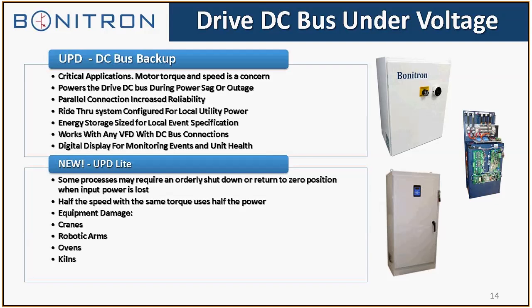What are the indicators doing? What are the lights doing? The digital display is also a diagnostic display. That's why I always recommend some sort of display. We have an analog version, but the digital display really tells you what's going on with the DC bus and the AC line, and it's almost a power quality meter. It does not measure power factor. That's the only difference, but it will tell you what happened during a ride-through event. It can also confirm the specification that you've sized the ride-through for.